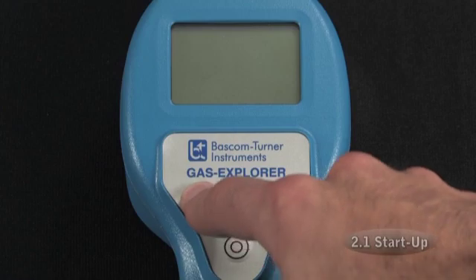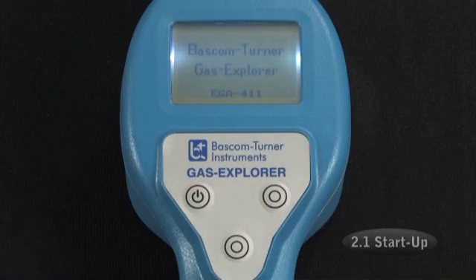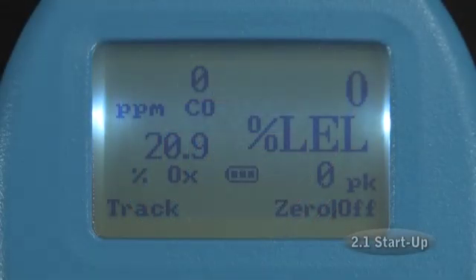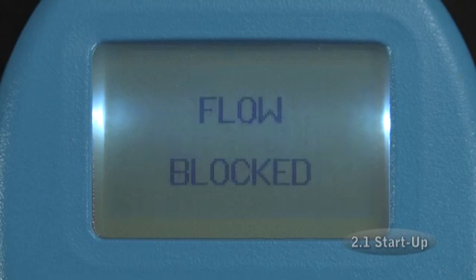During normal operation, the detector tests the pump about once a second to ensure flow is not blocked. If it is, the screen will show "Flow blocked" and the acoustic alarm will sound. You must remove the block to return to normal operation.